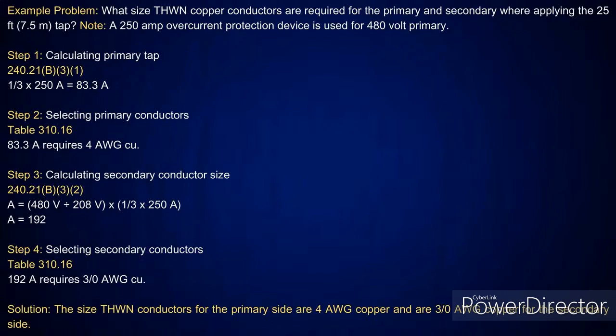Sorry. So if I look at step one, I do the primary. What do I take it at? A third. Yep. Gives you 83.3 amps. Go to table 310.16, pick up the 75-degree C column. It's going to tell you need a number 4, which is good for 85 amps. Now I'm going to do the secondary.